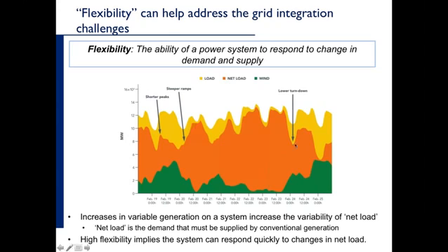And we also have several situations where we have lower turndown. In other words, at nighttime, we have a lot of wind right here on the diagram, and you can easily compare in the no wind case, we could turn down our generation, our thermal fleet, to around 10,000 megawatts, but now with all this wind that we have, we really would need to turn down our thermal fleet to something a little bit less than 8,000 megawatts. So I need the ability of turning down my thermal fleet lower than I used to have to turn them down. And so these are some examples of flexibility.